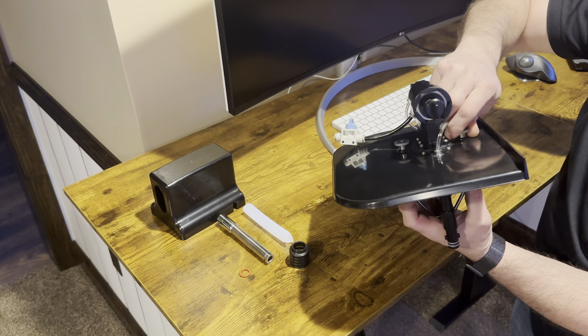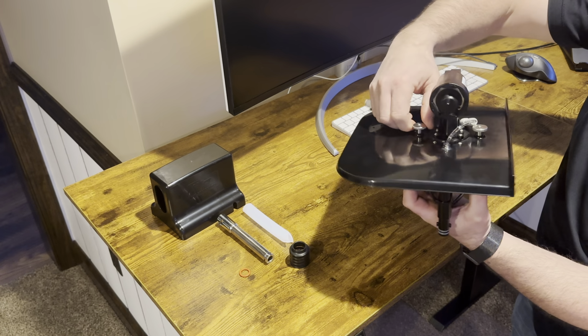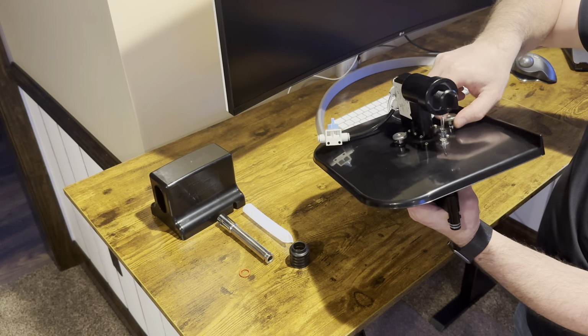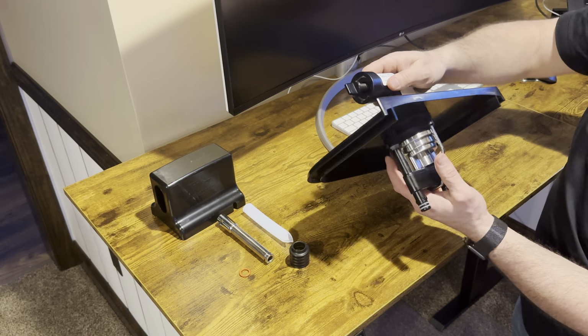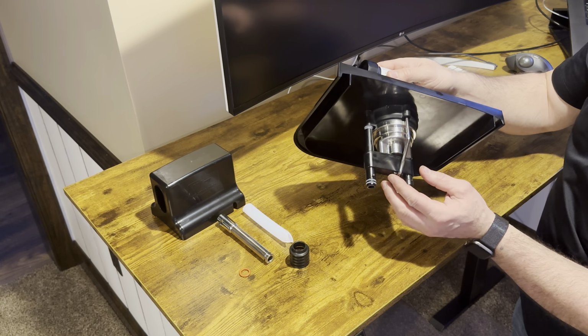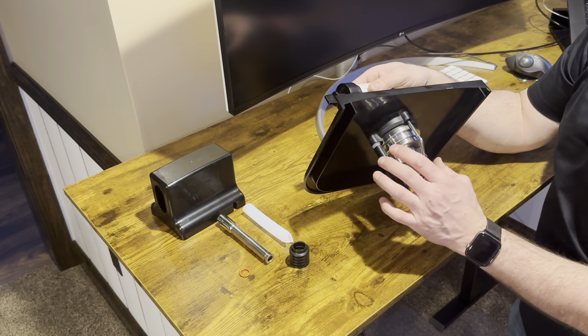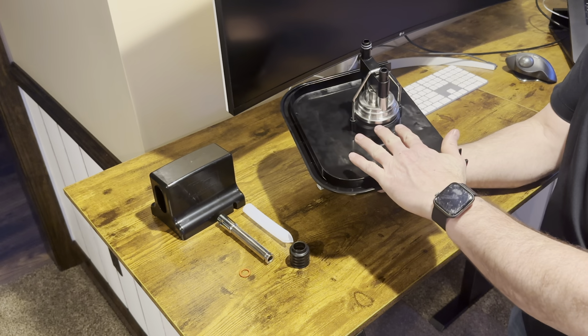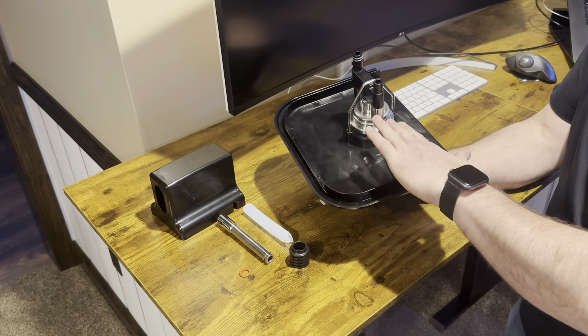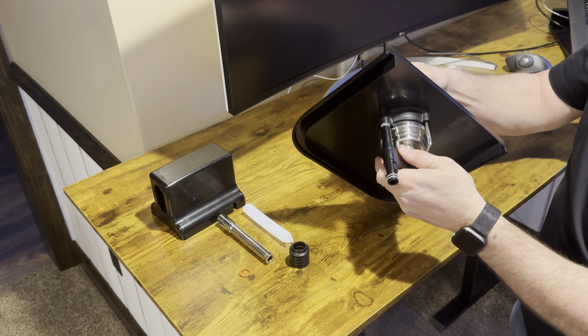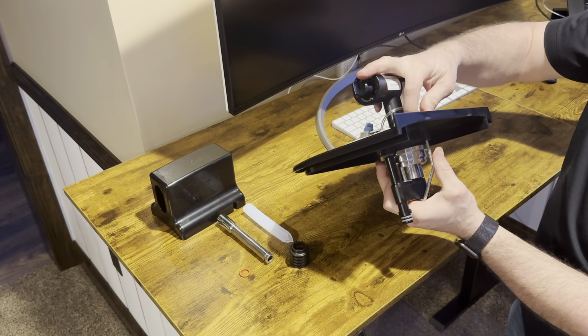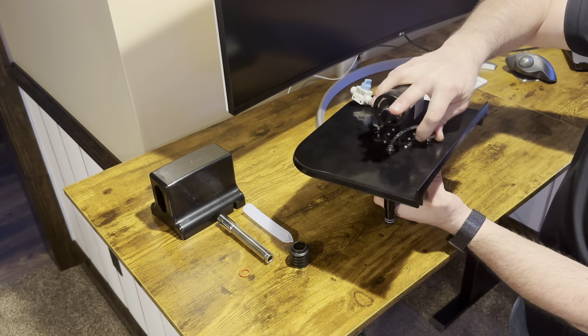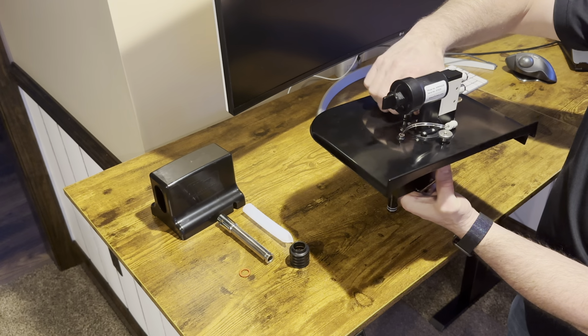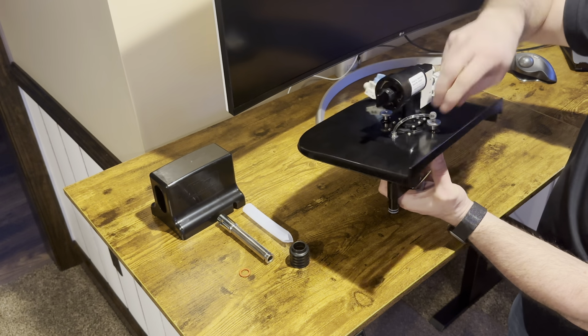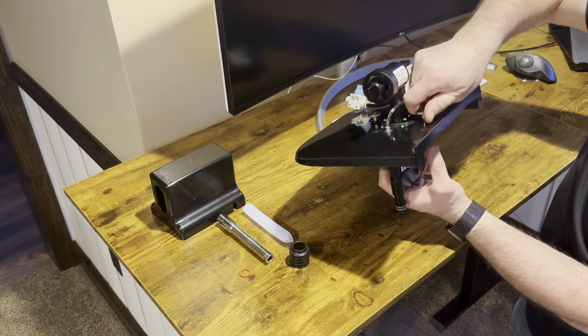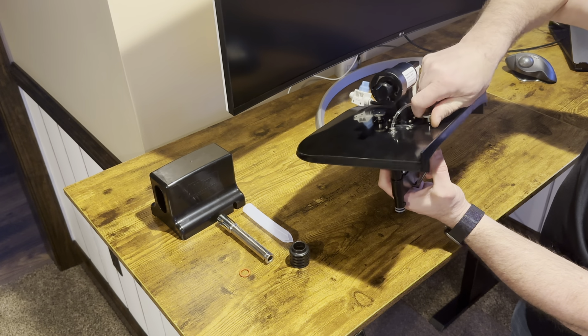And then alternating side to side, turn them down. And you'll want to pay attention here as this pulls together to make sure that the pump head is pulling down level and it's not getting tilted side to side. So usually works just to kind of gently press and wiggle a little bit there as you're tightening these one side and the other side, and you will pretty much want to go as tight as you can, going finger tight to draw that head down.